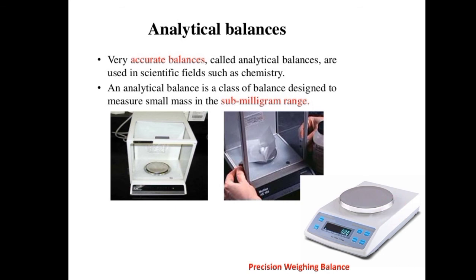The precision and the analytical balance are specific types of weighing balance which measure much smaller masses than the average scale. The analytical balance is the most used. It has higher reliability, measuring nearest to 0.0001 gram, and the analytical balance usually includes draught proof weighing chambers for measuring the mass, and is often used alongside anti-vibration tables to increase the accuracy.